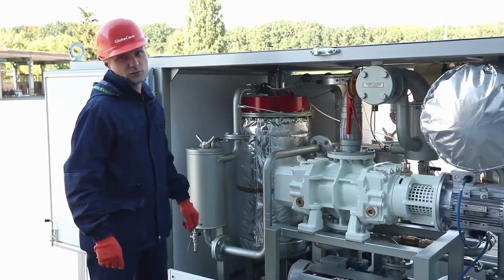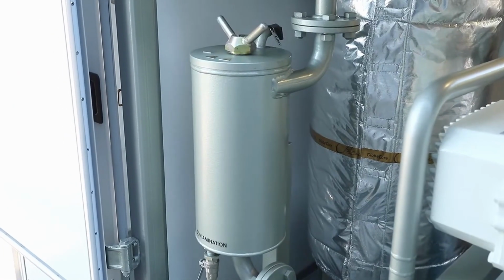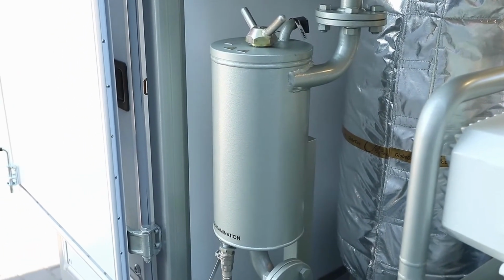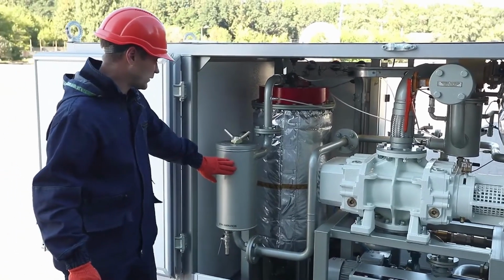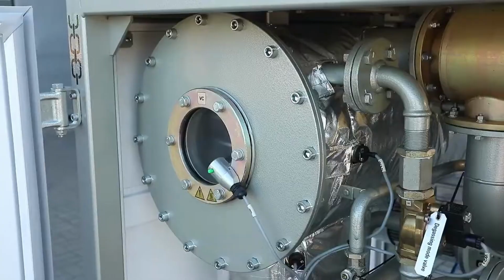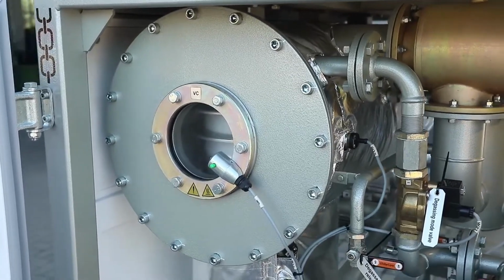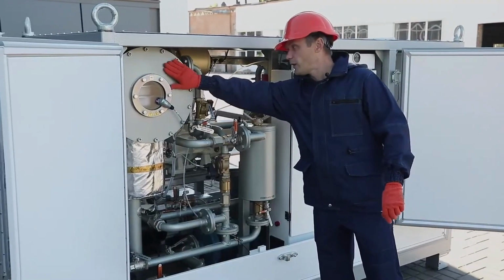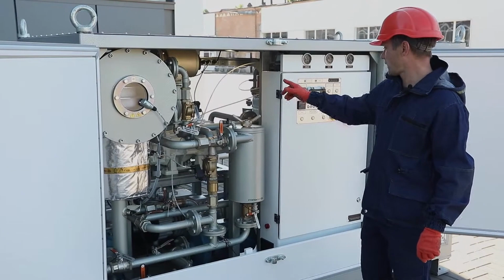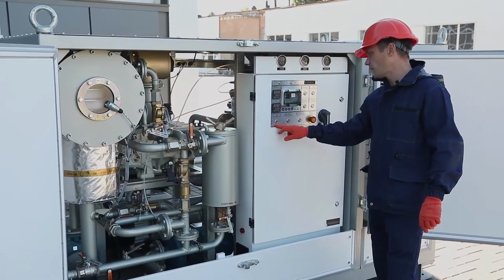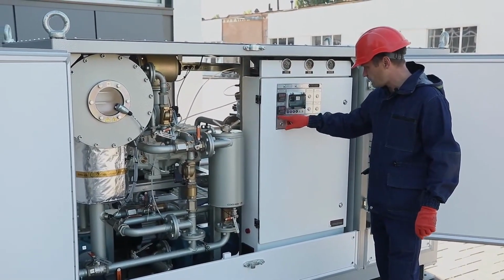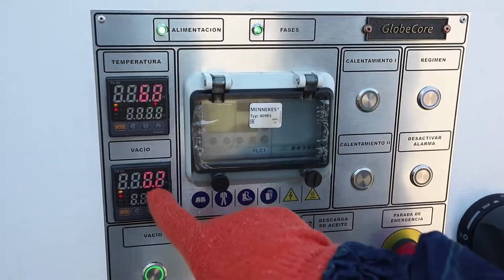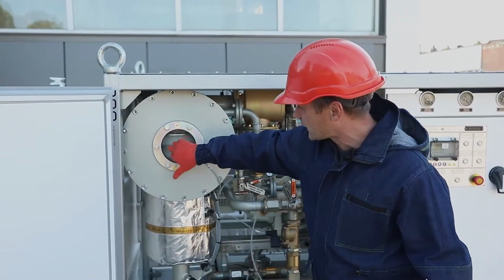Next, the oil goes through the first fine filter with the filtration fineness of 5 microns and is fed into the vacuum chamber. Due to the vacuum system operation, a pressure of not more than 2.5 millibars is maintained inside the vacuum chamber. The oil enters the activator filters and flows from the inside thereof to outside in a thin film from the surface of which water and gases are intensively released when driven by vacuum.